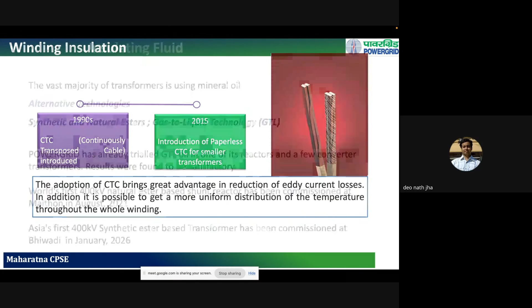In terms of insulating fluid, normally all transformers use mineral oil. The distribution transformers that you see in your localities and cities, up to 11 kV, also use vegetable oil as an insulation medium. But as the voltage goes up, the dielectric strength of the oil needs to be very high to withstand those high voltages. So in transmission EHV class transformers, we use processed mineral oil. Then in recent years, various alternative technologies have come up, like synthetic and natural esters and gas to liquid technologies.